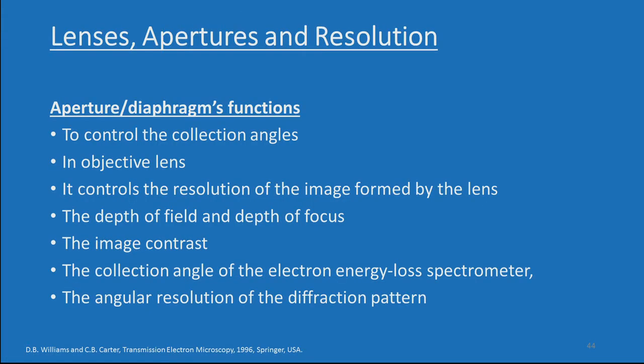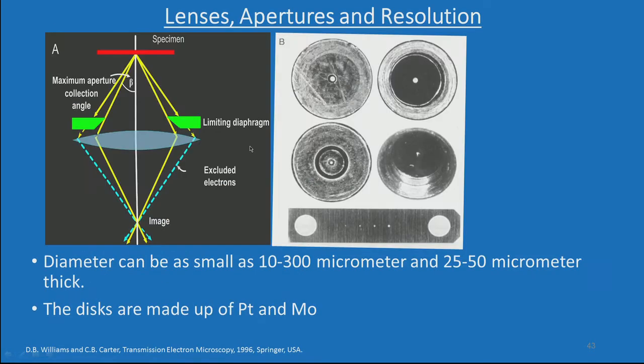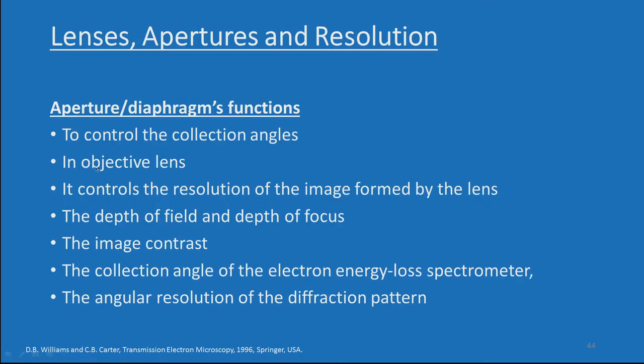What do apertures and diaphragms control? They control the collection angle beta. In objective lenses, they control the resolution of the image formed by the lens, the depth of field, and depth of focus. They also control image contrast, the collection angle of the electron energy loss spectrometer, and the angular resolution of the diffraction pattern. So apertures and diaphragms influence all these parameters.